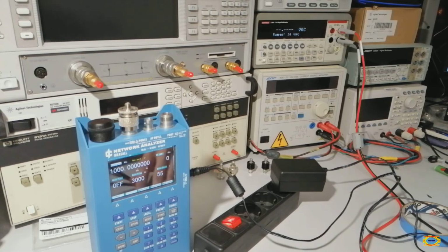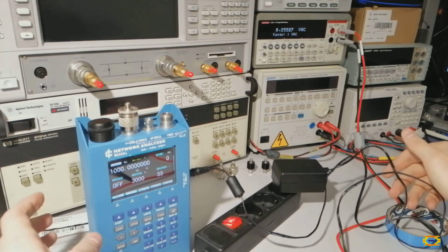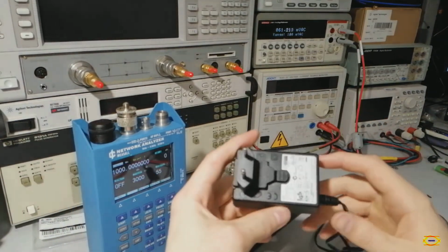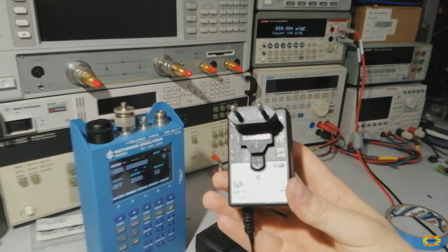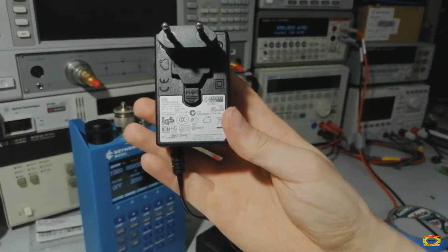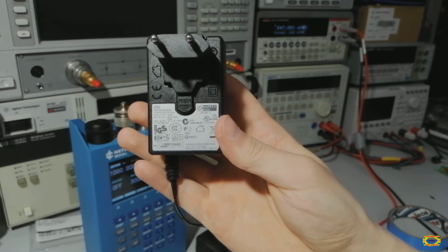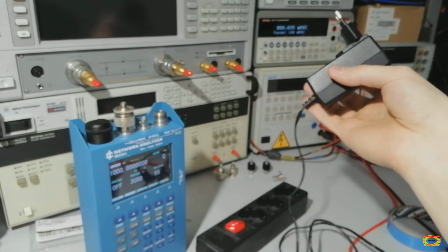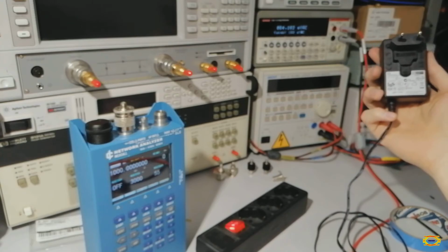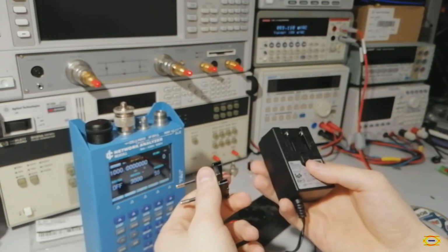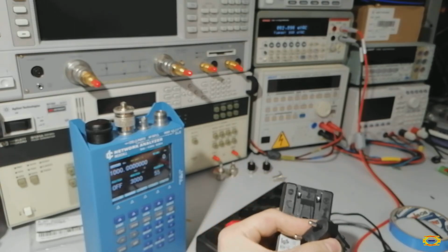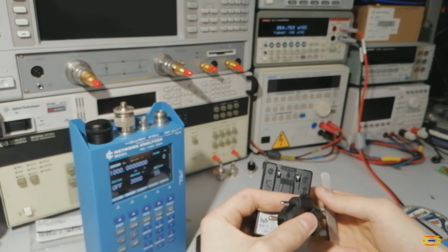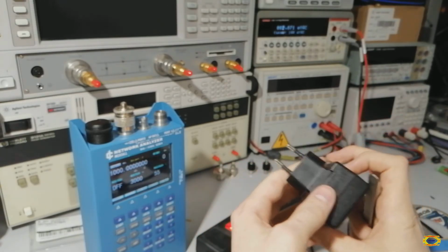I don't understand why you sell your high-priced device with that crappy power supply. Let me show you, Asian Power Devices Inc., with safety marks. You look at the safety marks. It's so safe for the instrument. You can easily avoid this by adding some earth connection over there. You really have to add your earth connection at the switching mode power supply.